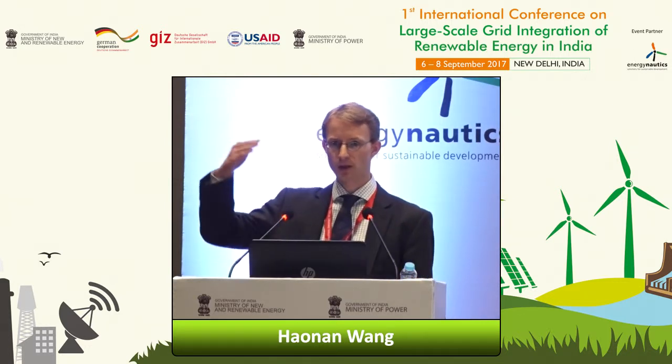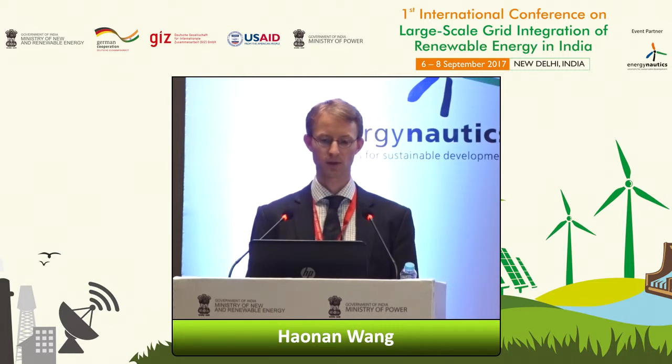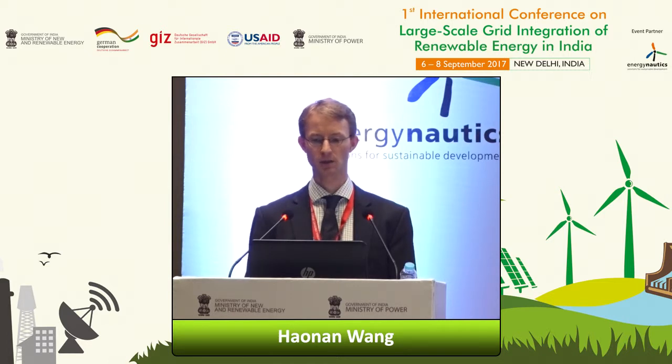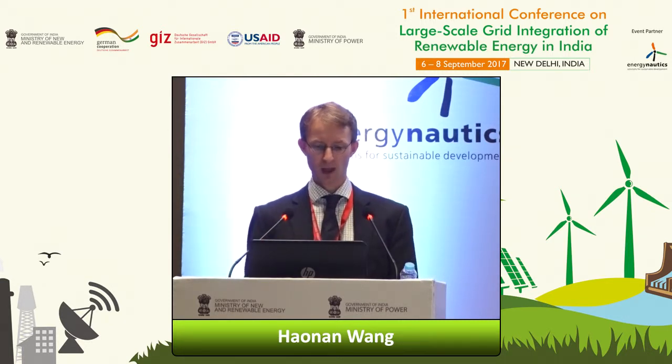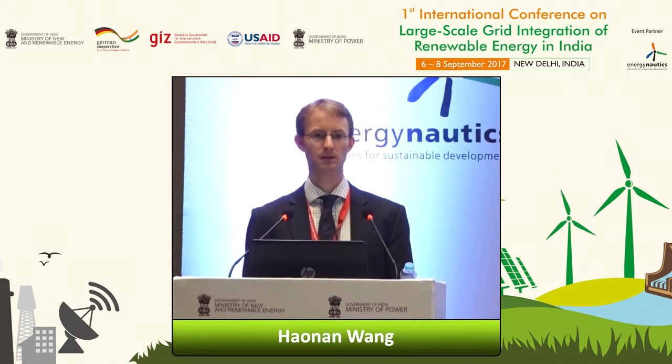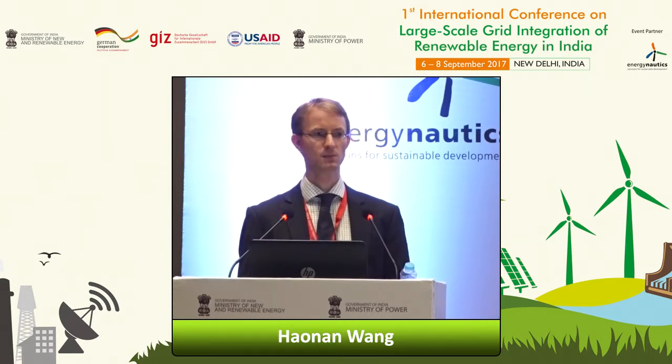Now, we did that also with regard to high voltage. What you see here is a simulation, but we validated it with measurements of active and reactive power points at the substations. Here it is a number of substations in a balance between the distribution system operator and the transmission system operator. We see the cloud of points, and in addition some limits. Now it is under discussion in Germany where those limits should be, and whether there should be any penalties or not. There are a number of projects, and we are involved in several of them, to analyze this interaction between distribution and transmission.